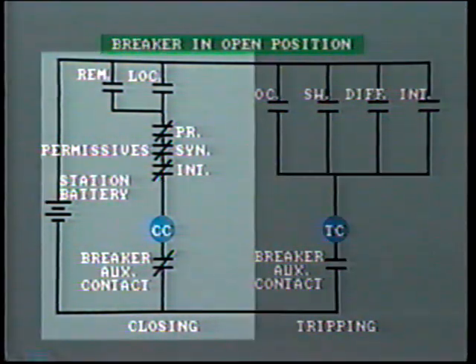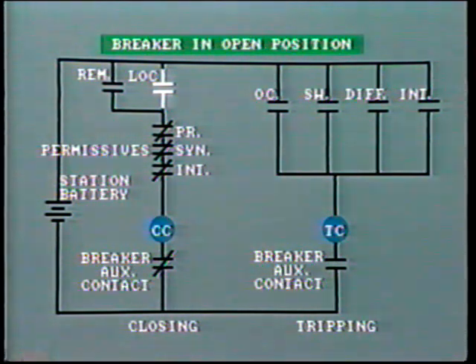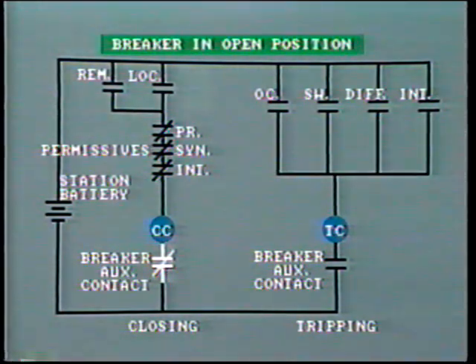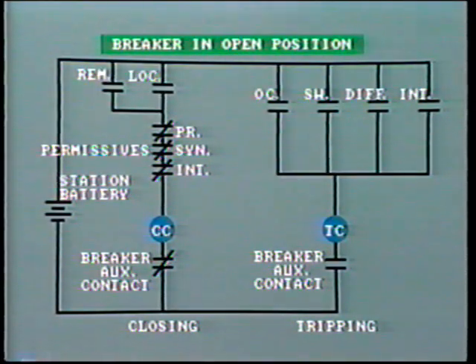Look at the closing circuit of this breaker. To energize the closing coil, the circuit must be completed by closing one or more of these pairs of contacts. This symbol indicates an open pair of contacts. Do not confuse this with the symbol for a capacitor, which looks like this. Now, a closed pair of contacts is shown by this symbol, and indeed, if they are closed under normal operating conditions, the letters NC may be added. Similarly, NO means normally open contacts. Conventionally, the diagram is shown with the contacts in the at-rest condition. That is, the tripping and closing circuits are de-energized. The circuit breaker is open.